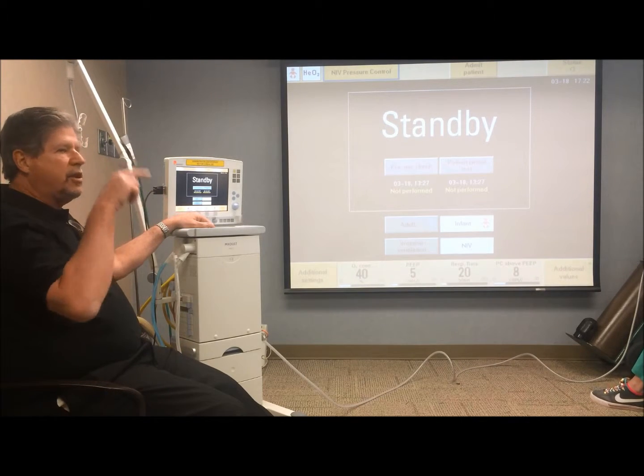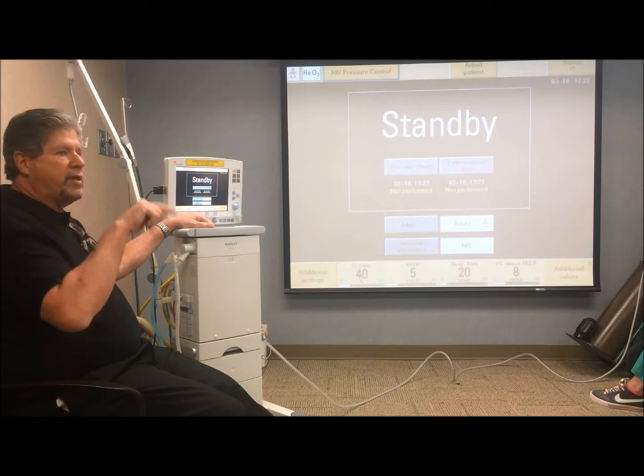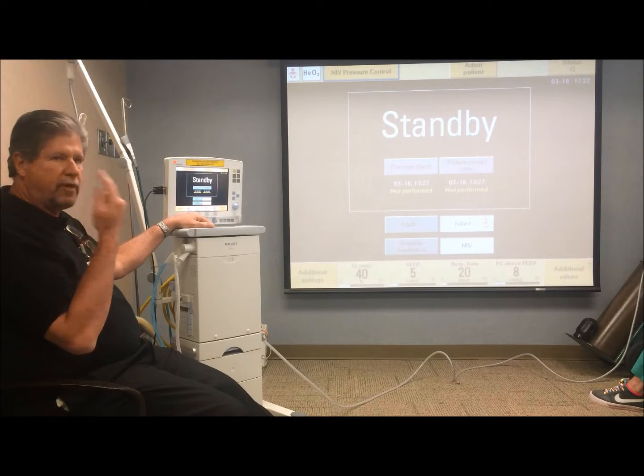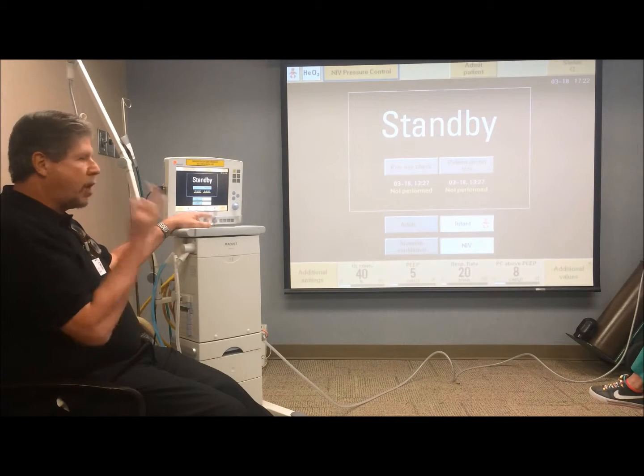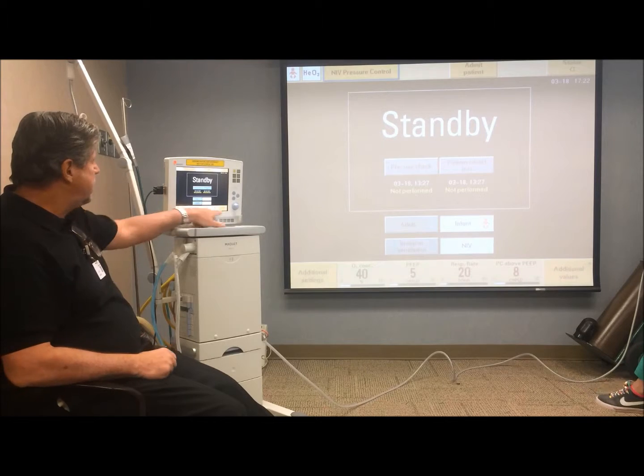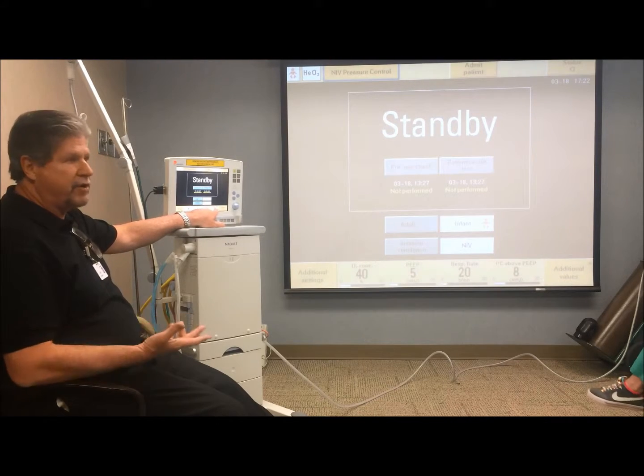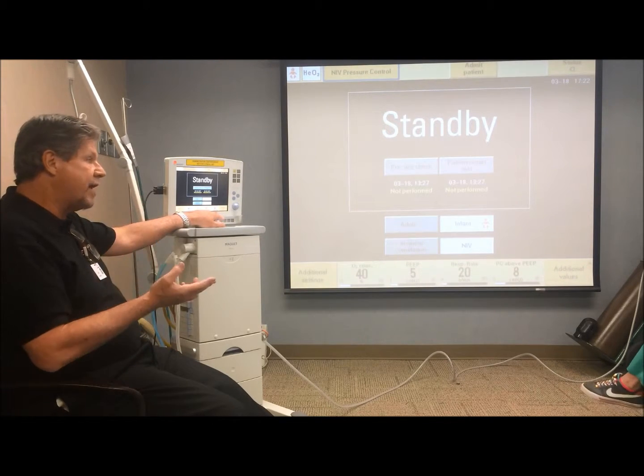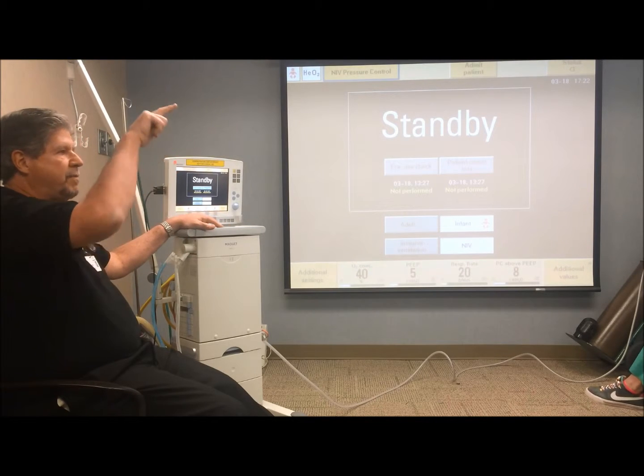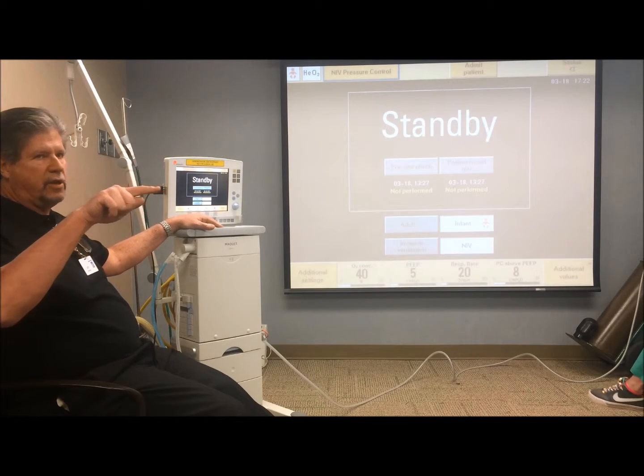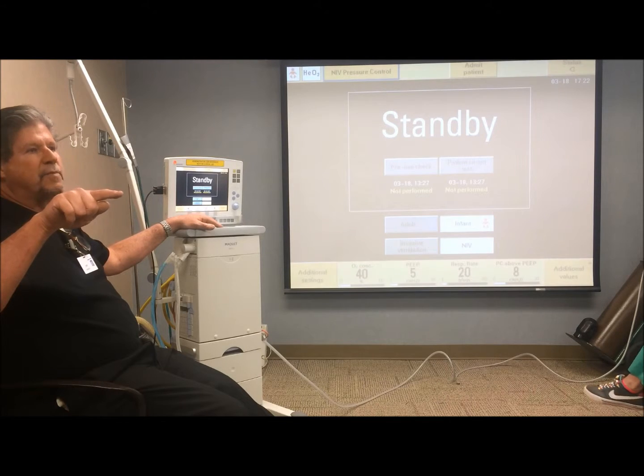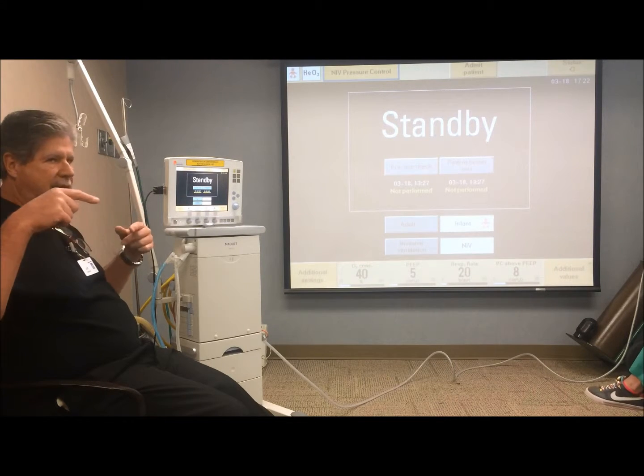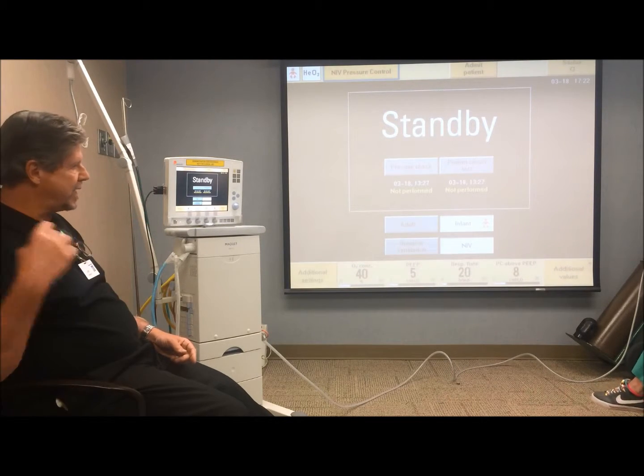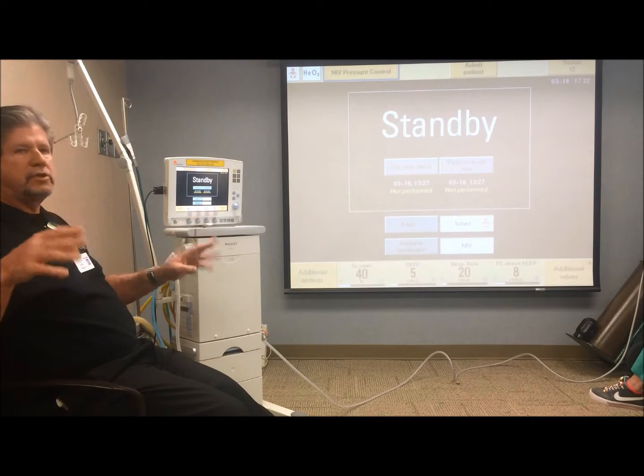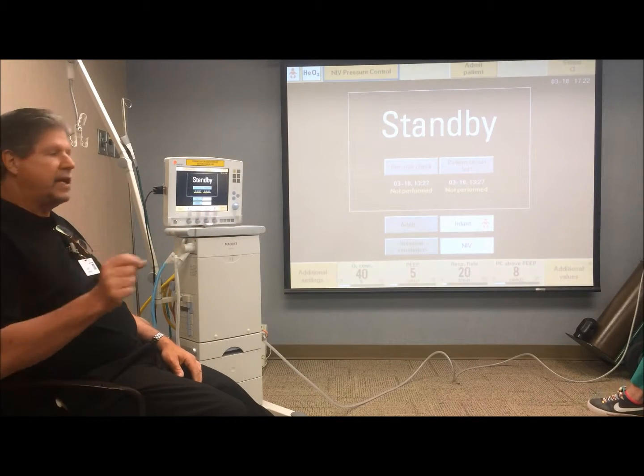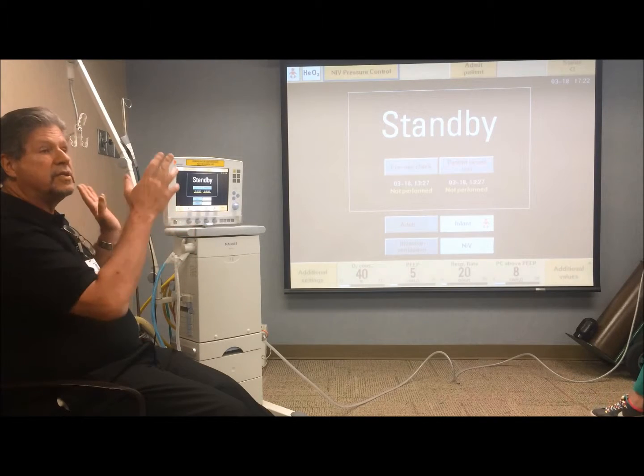So in between those 20 breaths, the kid is simply breathing CPAP. It's breathing the continuous flow that's running through the circuit, and then 20 times a minute the kid gets pinged with a pressure control breath of whatever you set, 8 or 10 or 5 or whatever. And if he stops breathing in between those breaths, the next mandatory breath that hits him is in essence similar to flicking the kid's foot with your finger, and he starts breathing again. So it's a stimulant. So people found this to be somewhat successful.